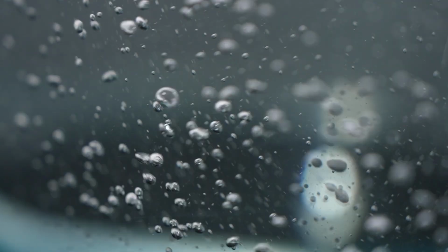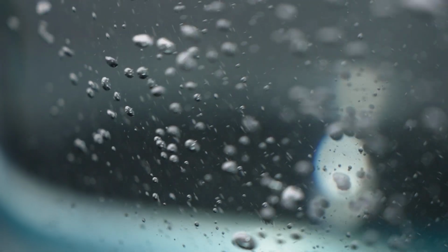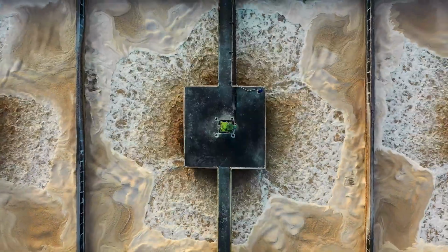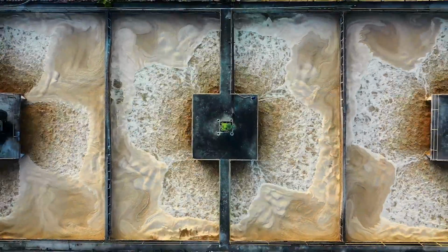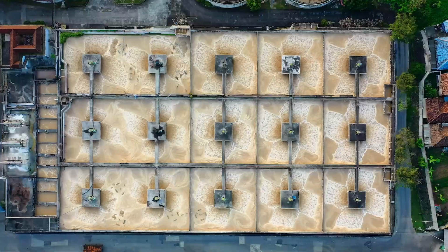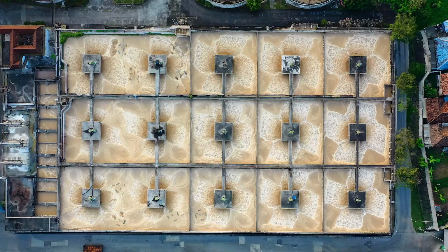If you go straight to the heart of a wastewater treatment plant, the aerobic zone, the aeration basin, you need to provide air. That can be done today with 2 different types of arrangement. Either you're going to use mechanical aeration. Surface aerators, you have aerosols, you have odour emissions from the tanks, you have poor performance from some of those aerators in terms of the kilograms of oxygen output that they can do.